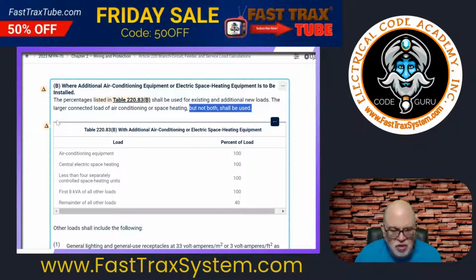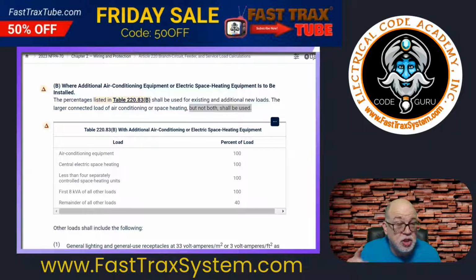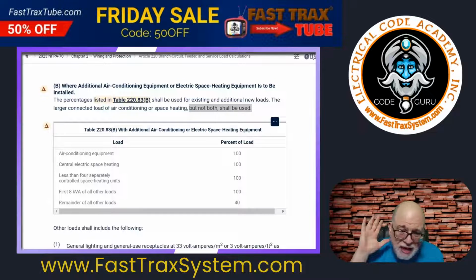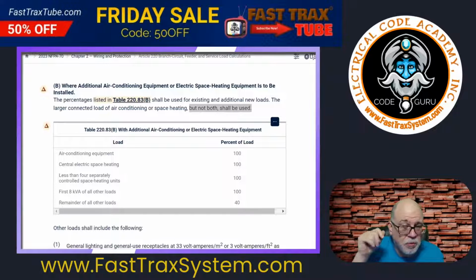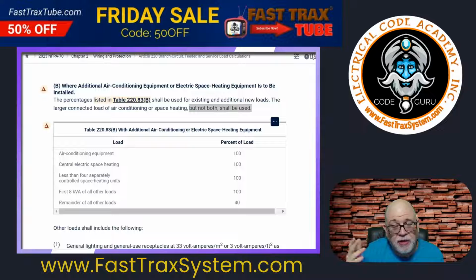Okay, so let's look now. I'll give you a look at what it's going to look like in the 2026 edition. Hopefully this is not confusing. The easiest way I can tell you is to just do the optional method like in part A, as you normally would in this example, and then take the heating or the air conditioner, whichever is larger, and then add that at 100% and add that to the totals that you got when you did the first 8,000 at 100 and the remainder at 40.